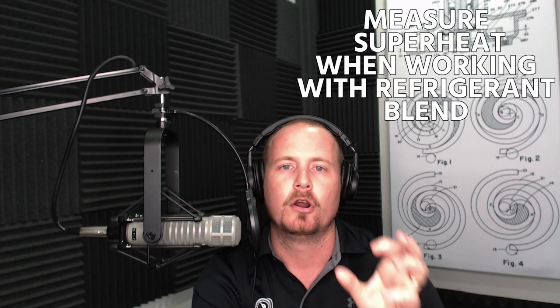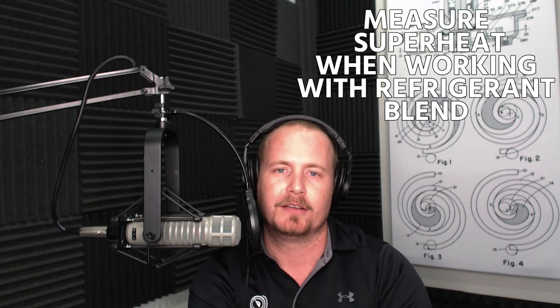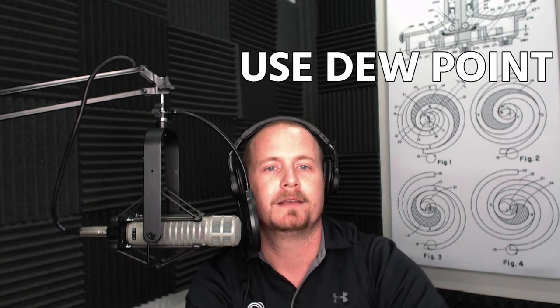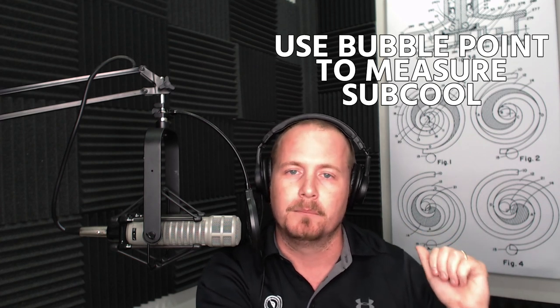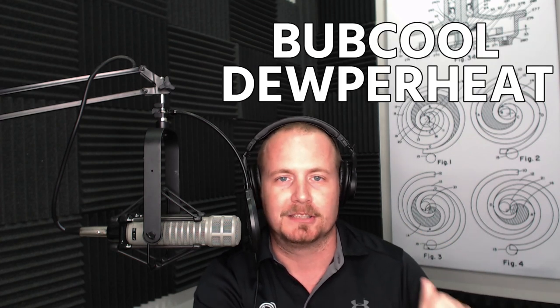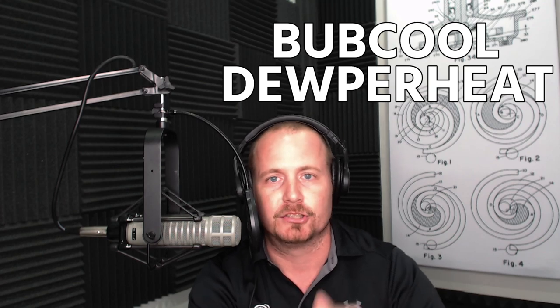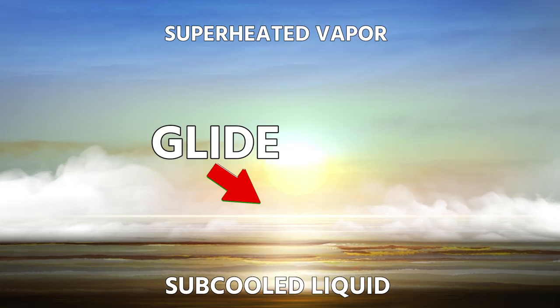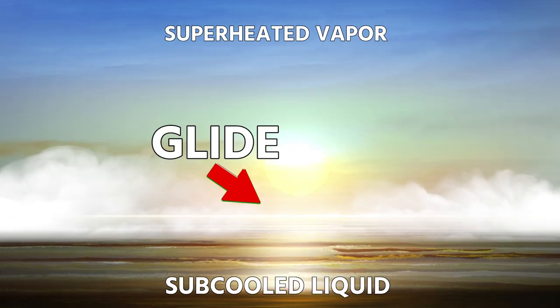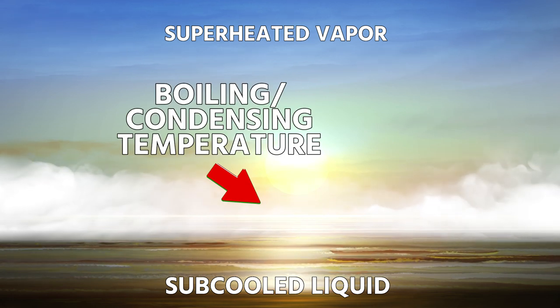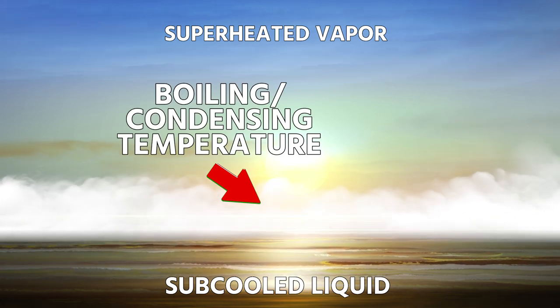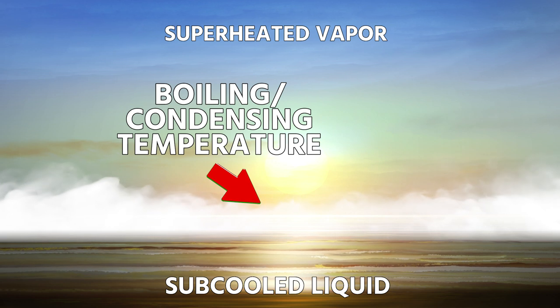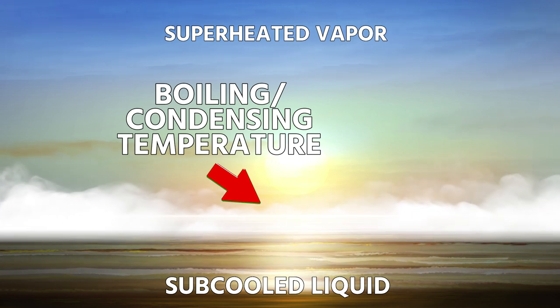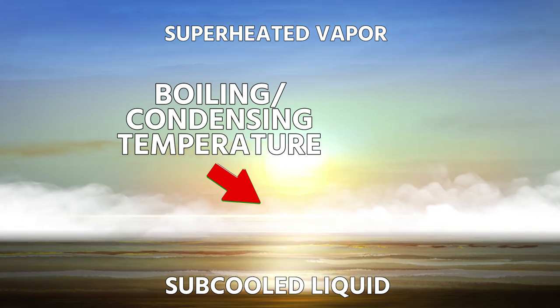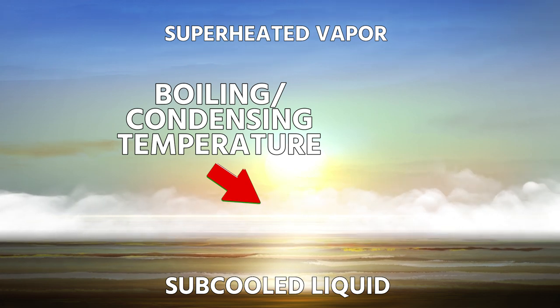And so if you're ever working with a refrigerant blend and you're having to measure superheat, you use dew point. To measure subcool, you use bubble point. And that's easy to remember because it's Bubcool and Dewperheat. And just remember that that glide is like having a wider horizon. The boiling or condensing temperature is now a band, unlike a single component refrigerant or an azeotrope, where that is just a single line, a single point at which that condensing temperature or boiling temperature occurs at that pressure.